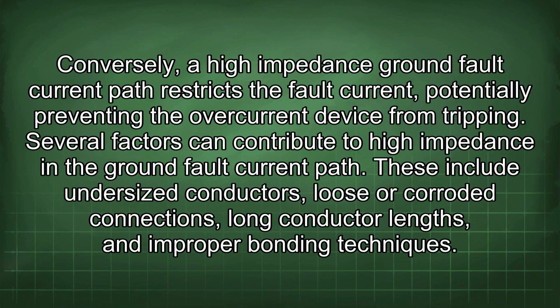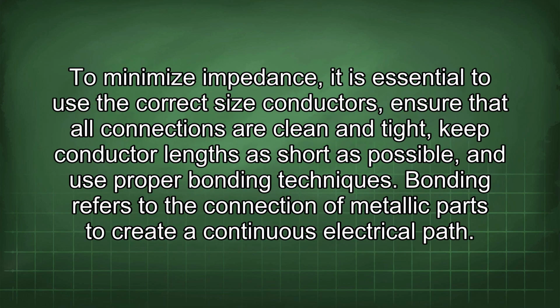Several factors can contribute to high impedance in the ground fault current path. These include undersized conductors, loose or corroded connections, long conductor lengths, and improper bonding techniques. To minimize impedance, it is essential to use the correct size conductors, ensure that all connections are clean and tight, keep conductor lengths as short as possible, and use proper bonding techniques.